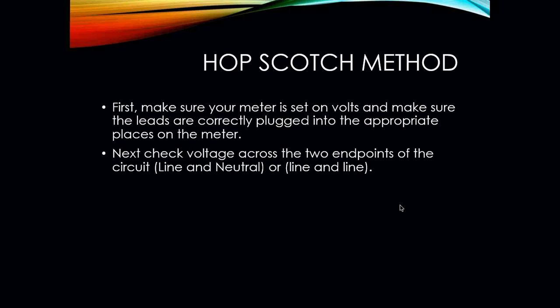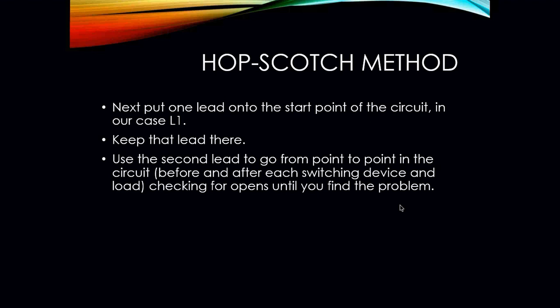So first, when we are doing the Hopscotch method, you have to make sure that the meter is set to volts, and make sure that the leads are correctly plugged into the appropriate place on the meter. Then next, you're going to check voltage across the two endpoints of the circuit, and in this case, line 1 and neutral, or line to line. Next, you are going to put one lead onto the starting point of the circuit, and in this case, it's going to be L1. And then keep that lead there throughout the entire time that you're troubleshooting the circuit. You are now going to use the second lead to go from point to point in the circuit before and after each switch device and load, and check for opens until you find the problem.